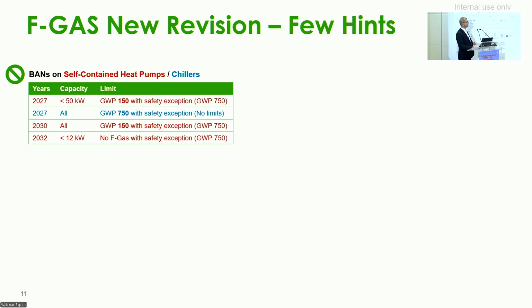When we talk about bans in the new F-gas, we have this summary table. In red, you can see self-contained heat pumps, meaning monoblock heat pumps, not split. And for them, there is a limit from January 1st, 2027 of 50 kilowatt. All heat pumps below 50 kilowatt will have a max GWP permission of 150. From 2030, this limit will be extended to all capacities. And from 2032, all heat pumps below 12 kilowatt will have no F-gas permission.